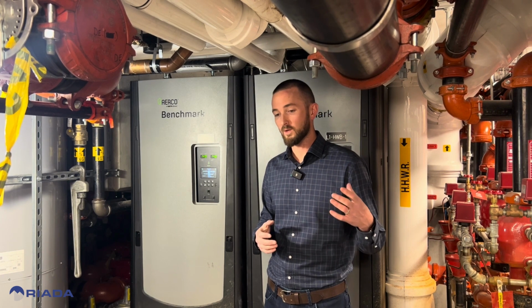Now, typically, boilers are rated on their spec sheets to an efficiency rating which is for a 100-degree delta T at max fire from 80 Fahrenheit to 180 Fahrenheit. And that means all boilers appear on a spec sheet to be mid-90s in terms of thermal efficiency. Same with AERCO. However, where we really shine, especially in the Lower Mainland and Vancouver Island, where we're often running at part load, not at our peak winter design, is what we call seasonal efficiency, when the boilers are at part load conditions.